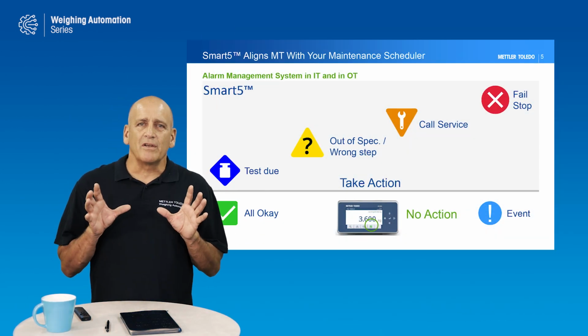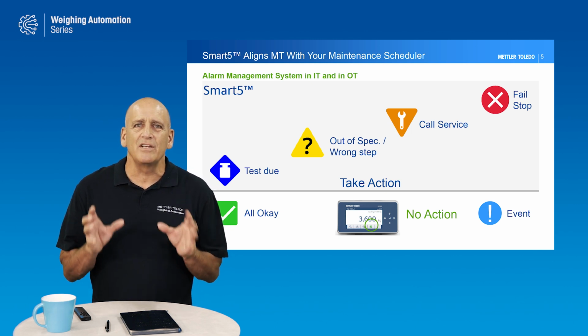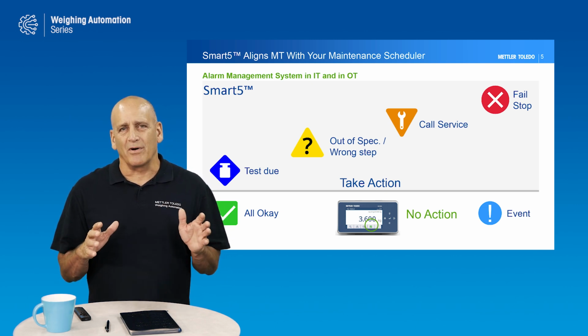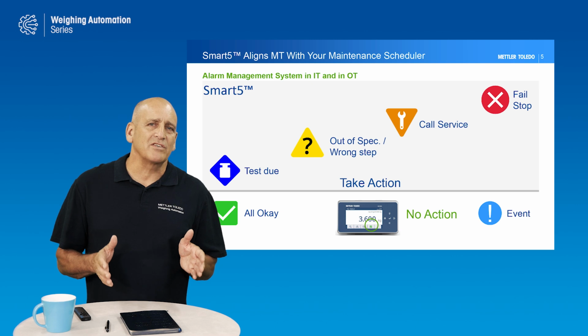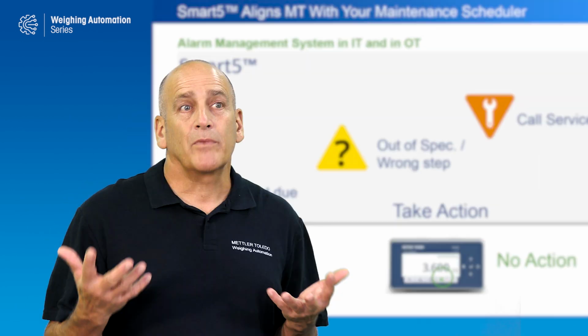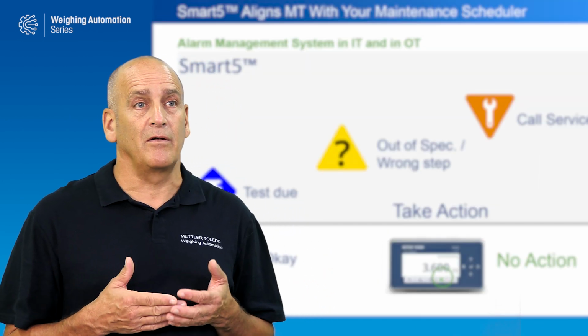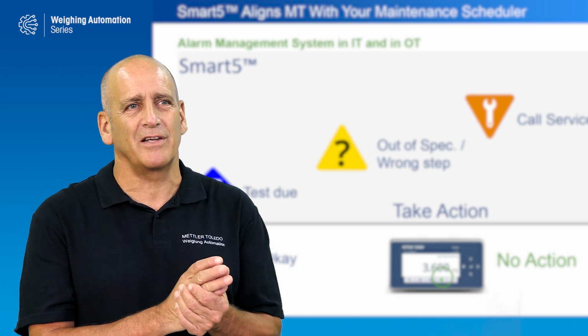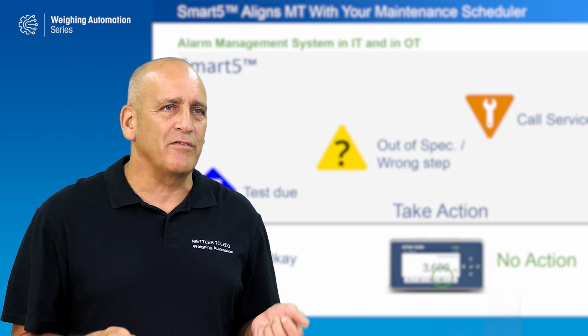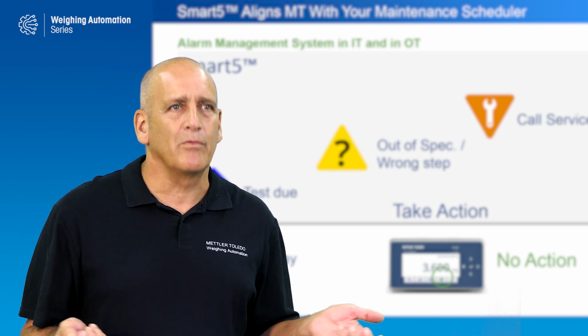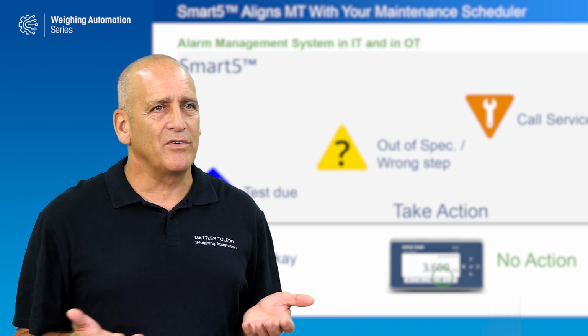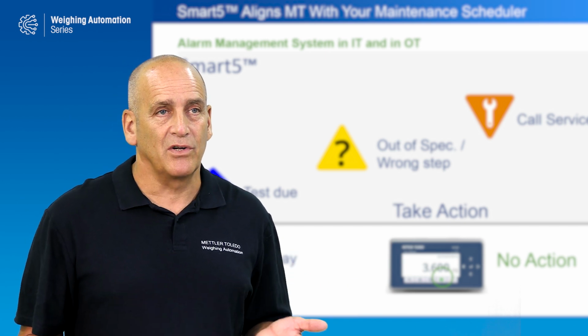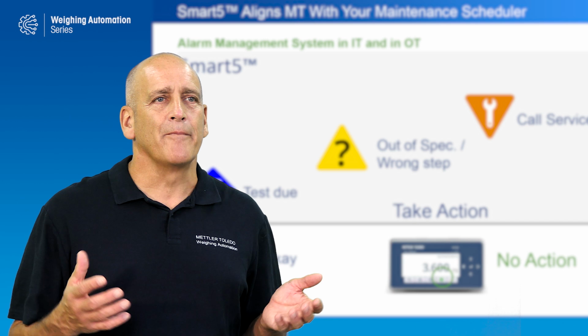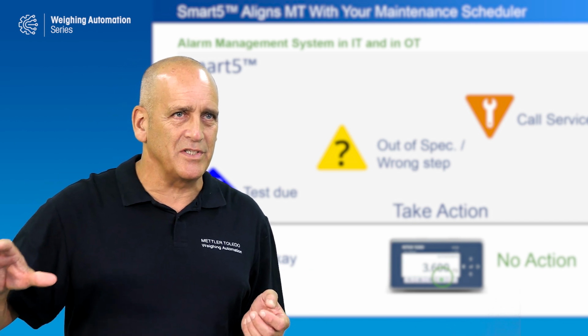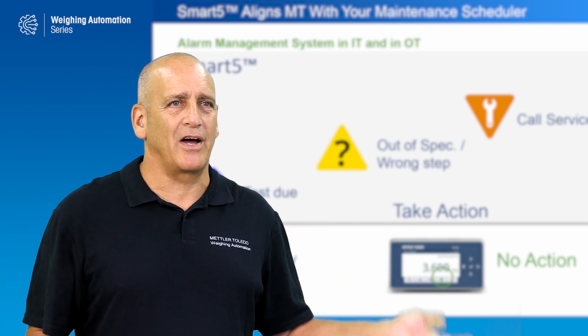And then finally, the red level tells you that there's something completely wrong with the process and you need to start over, or you need to stop the process. You need to take corrective action to make the thing go away. For example, if a load cell cable would be cut, a forklift is driving by, it cuts the cable, it breaks. If it's a PowerCell, you can replace the cable and you're back up and running without having to ruin your batch. So this allows you to take action right away. And that action gets trapped, as we said, in your PLC, DCS, or your IT system.